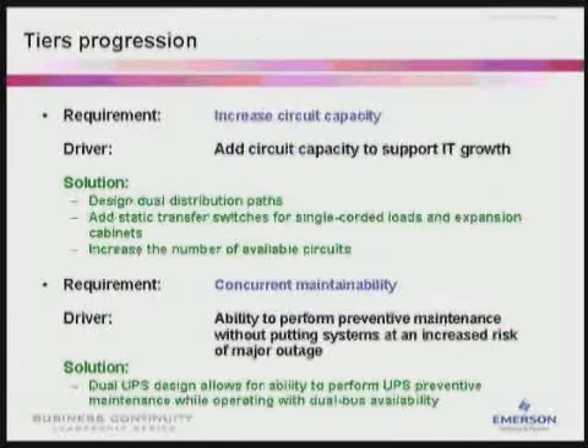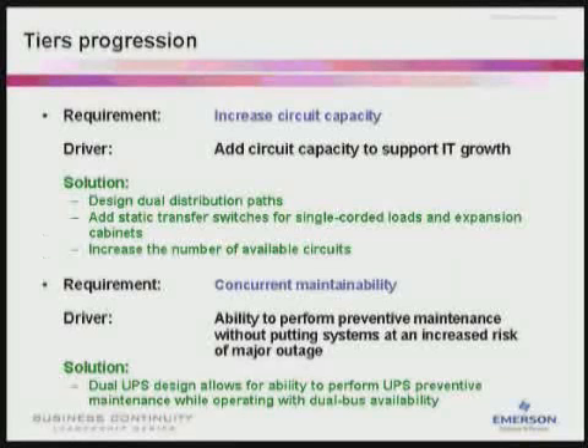Increased circuit capacity was needed to support IT growth. The solution was to design dual distribution paths using static switches for single-corded loads and increasing the number of available circuits. The ability to perform preventive maintenance was also a critical addition, without having to put the systems at increased risks of major outage. A dual-bus UPS design allowed for the ability to perform UPS preventive maintenance while operating with dual-bus availability.